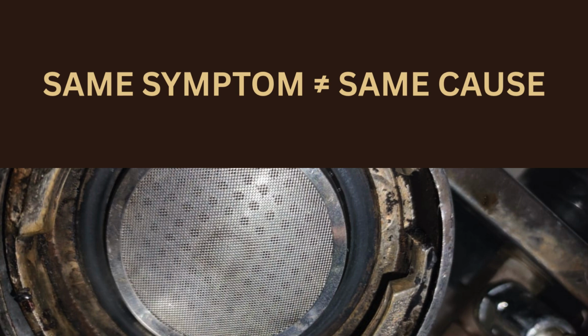For example, low pressure alone does not automatically mean the pump is bad. Pressure behavior must be analyzed alongside flow rate, extraction speed, resistance, machine sounds, maintenance history, and system condition. The same symptom can come from completely different causes depending on context. This is why random repairs often fail. People treat the visible symptom while ignoring the deeper system behavior underneath it. Technicians avoid this by thinking in probabilities instead of assumptions. Every symptom either strengthens or weakens certain possibilities until the problem becomes logically isolated.